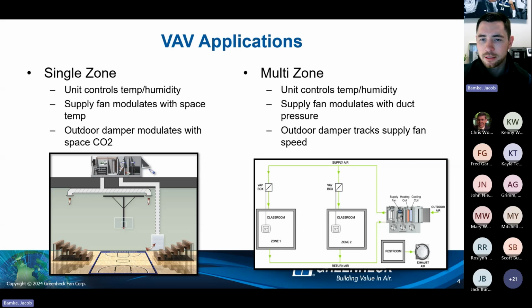Problem is, on low sensible days where you don't need as much air from a sensible standpoint, it's a little bit harder to control the humidity that might be building up in the classroom with the DOAS equipment. And because you're modulating your supply fan, but in these situations you still need a minimum outside air percentage, typically we're seeing the outdoor damper track that supply fan speed. So as that supply fan ramps up and down, the outdoor damper will readjust positions as well to make sure we hit those minimum ventilation rates.